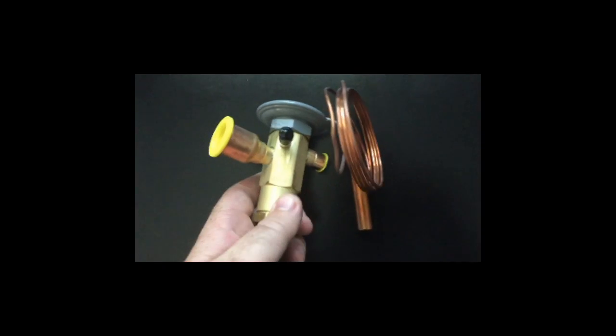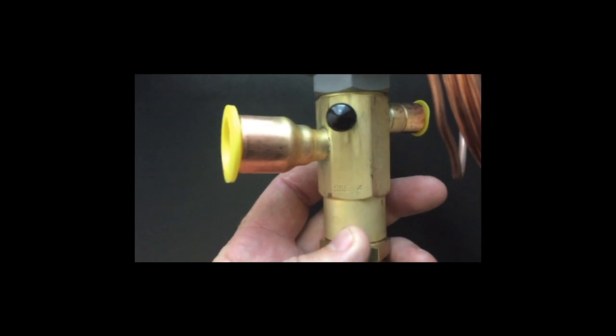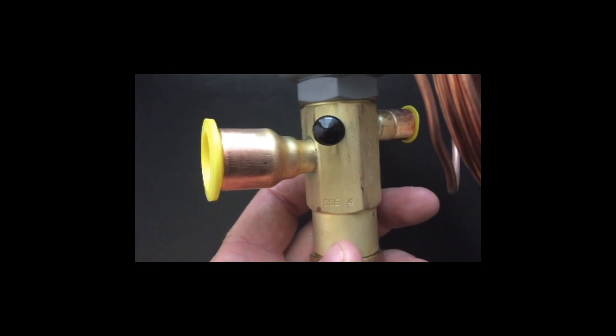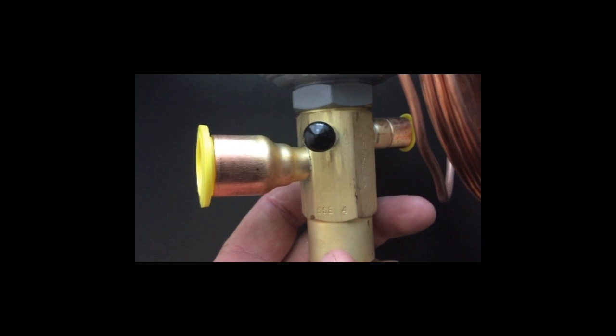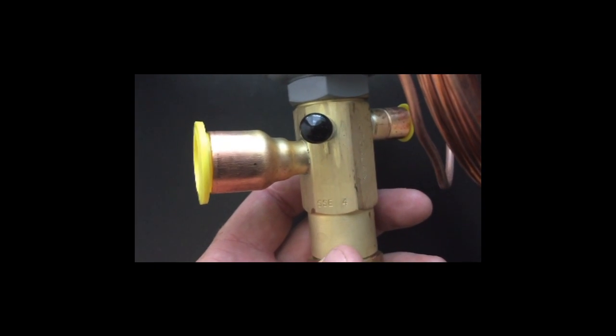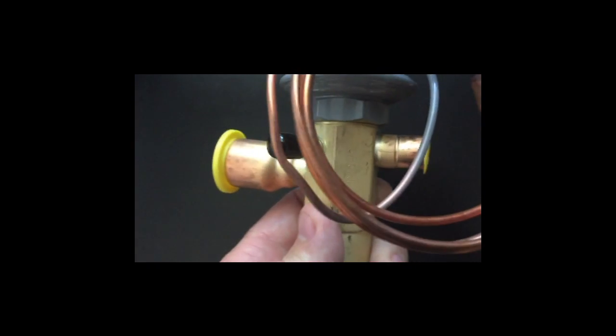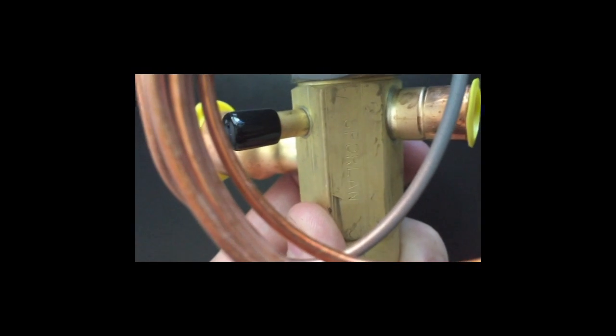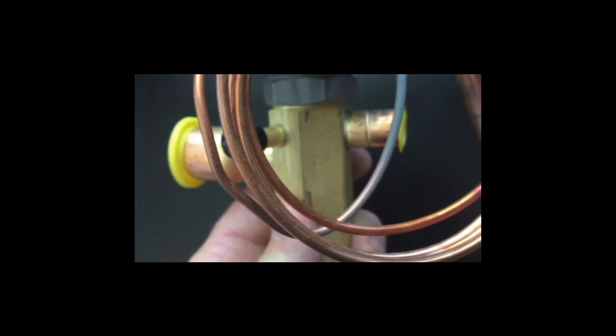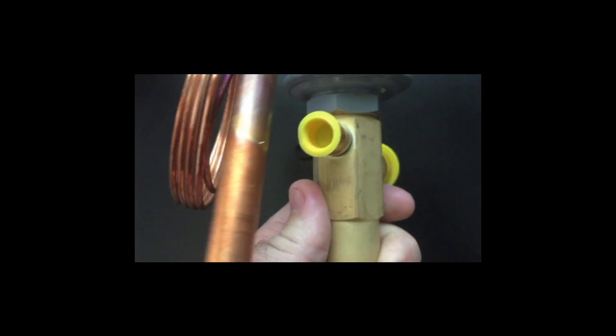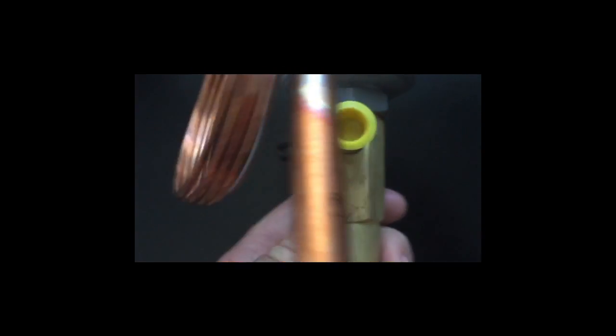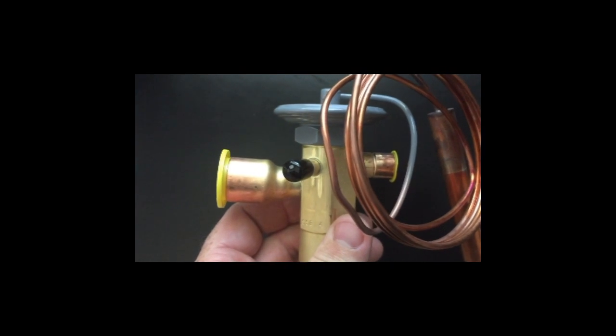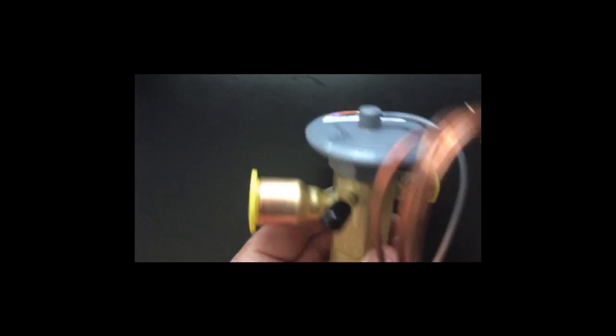First of all, you'll notice that it does come marked. This is an S body valve, a nominal 4 tons, a particular SSE-4. It's labeled with the Sporlan name right there if you can grab that on the camera. And also, you'll see that this is the inlet labeled. So this particular valve is a half-inch inlet and a 7-eighths outlet.